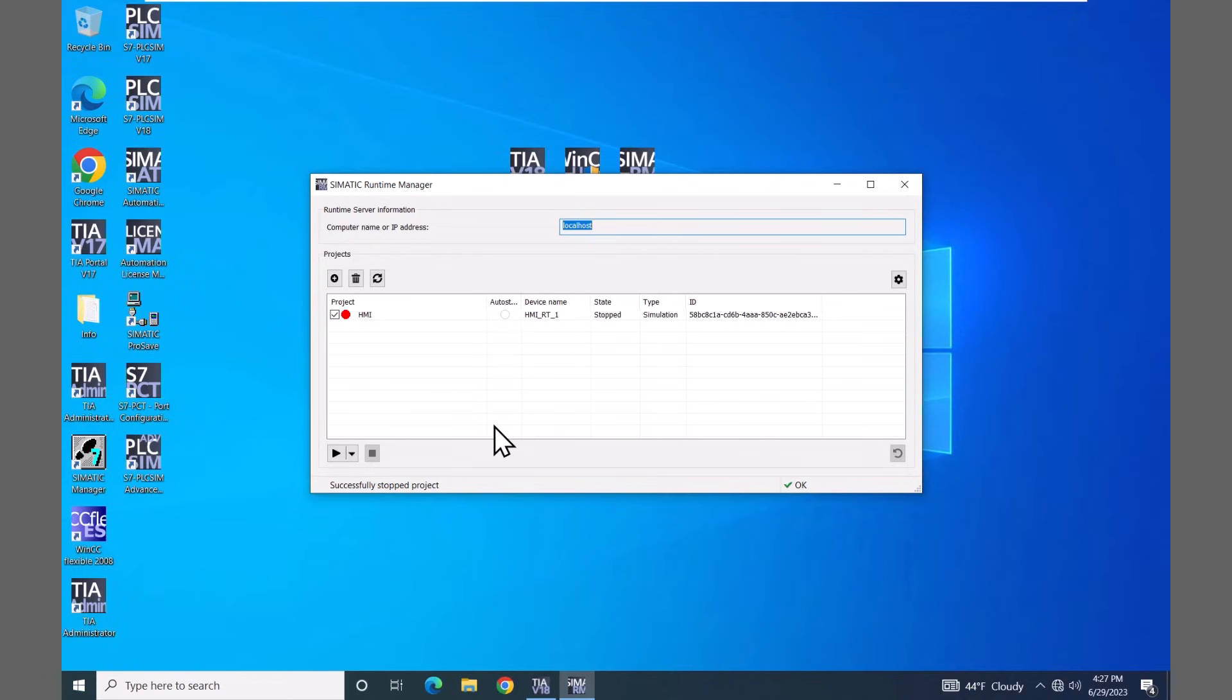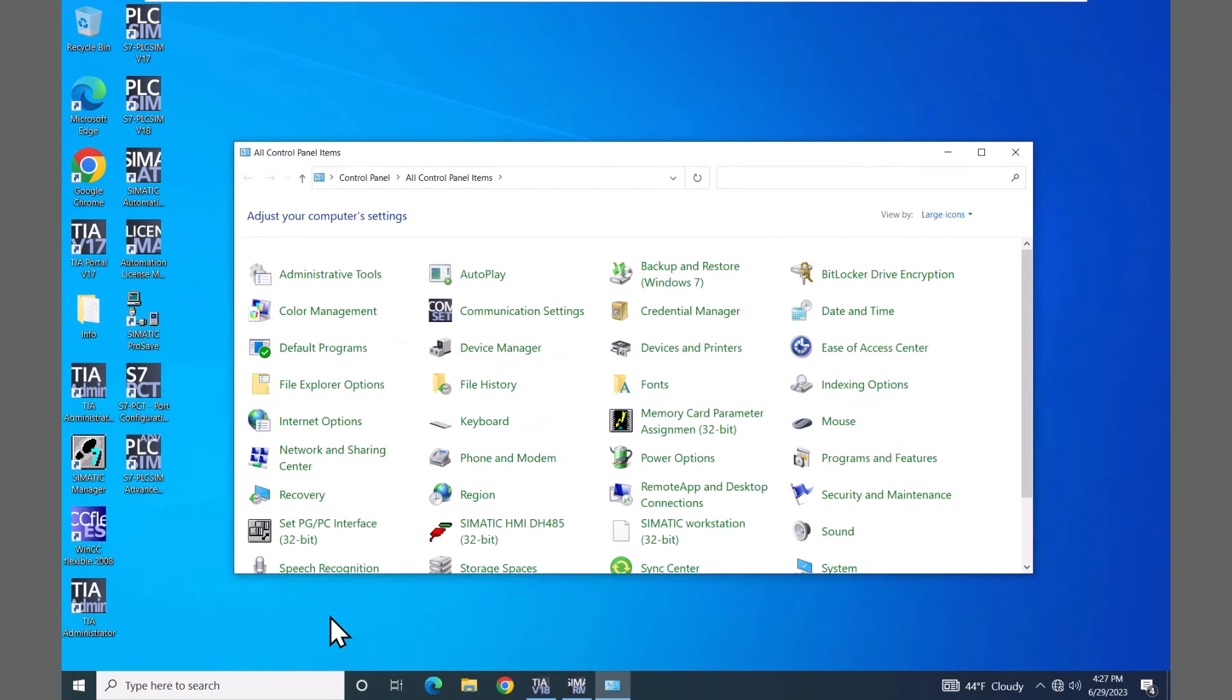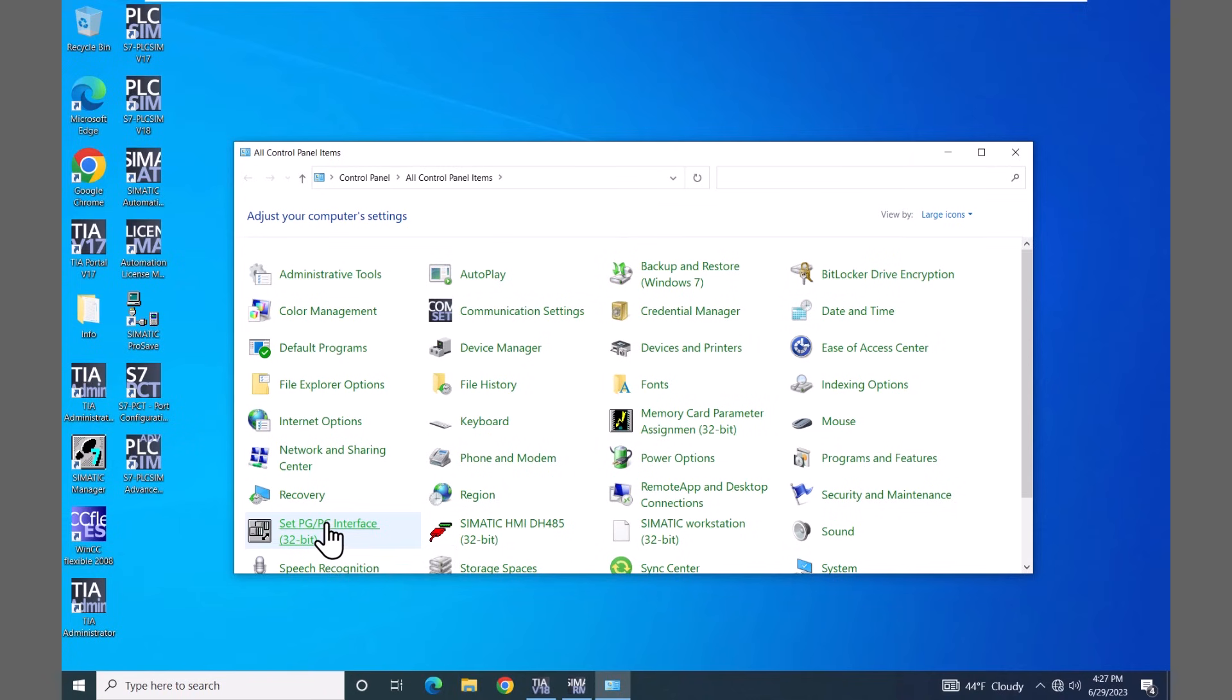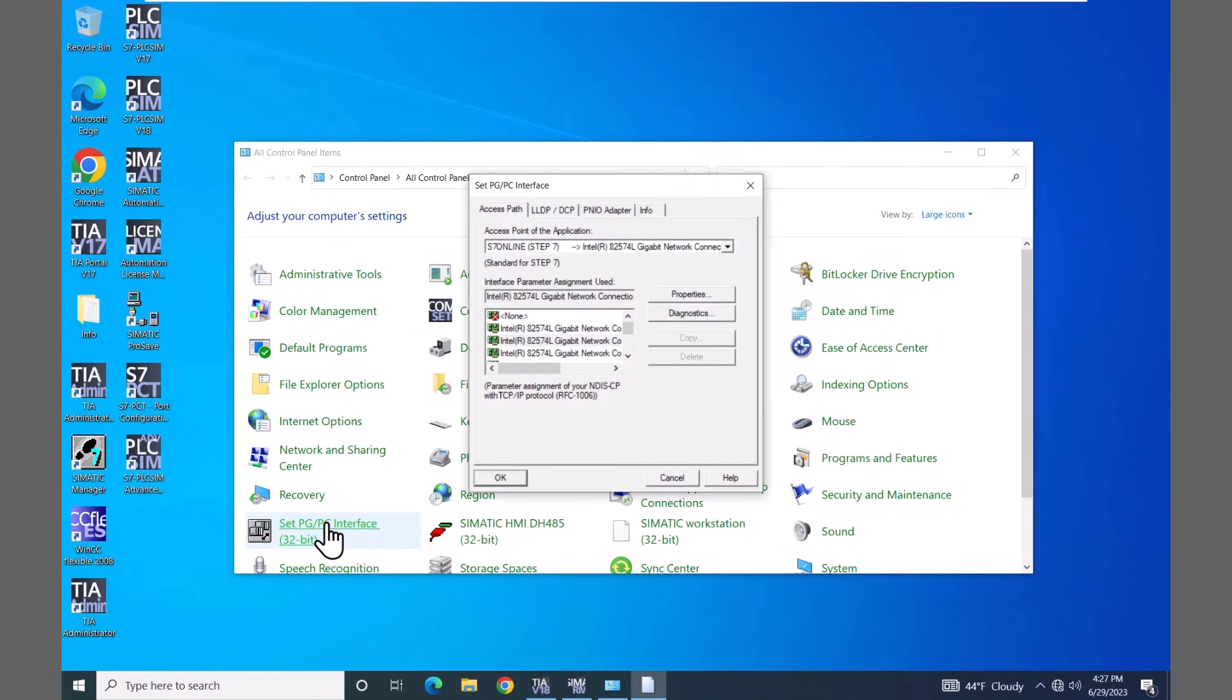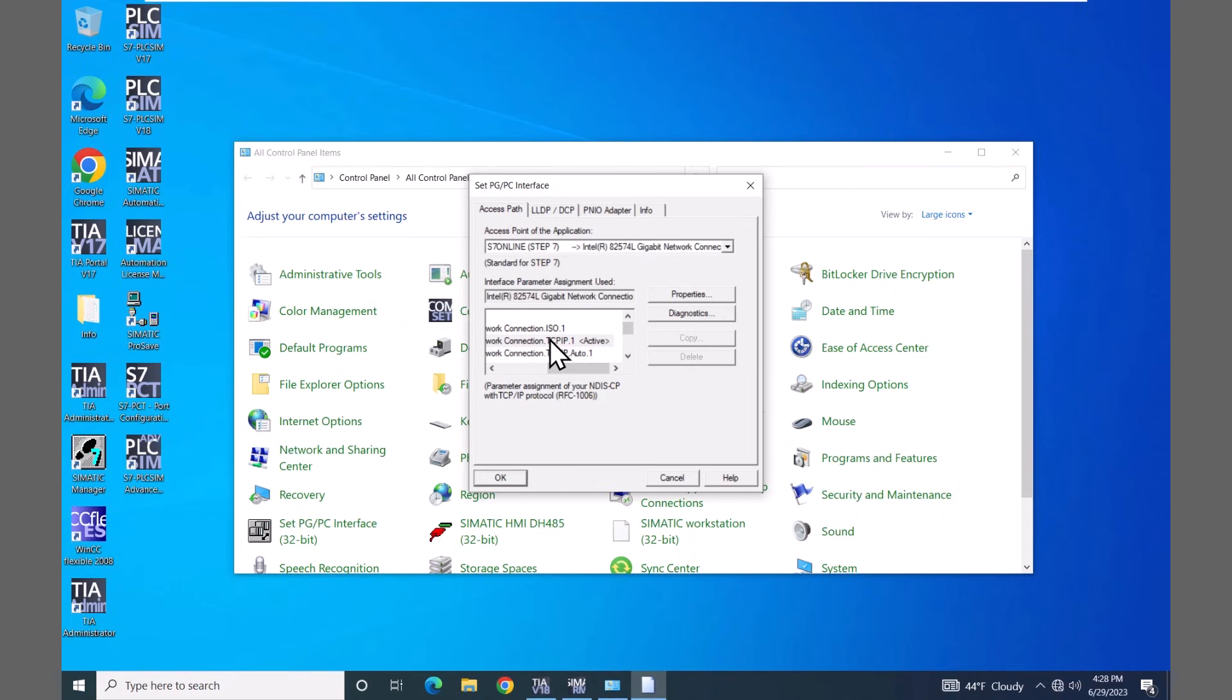We have not configured a PLC yet for simulation, but the runtime simulation is also able to connect to a real world PLC. I will open up my windows control panel and there's an entry in here that is called the setPGPC interface. This setPGPC interface is going to define what physical connection the simulated HMI will use to talk to a real world PLC. So the S7 online is the logical interface and then this Intel network adapter is the network adapter that I have selected for doing the communication. So it's going to be the TCP IP connection. So in a future lab when we do actually add in the S7 1500 PLC, we will be able to go online and talk to the real world PLC with the simulated unified comfort panel.